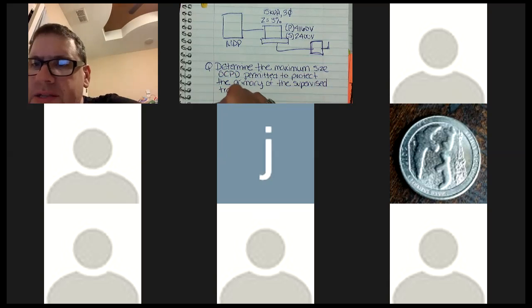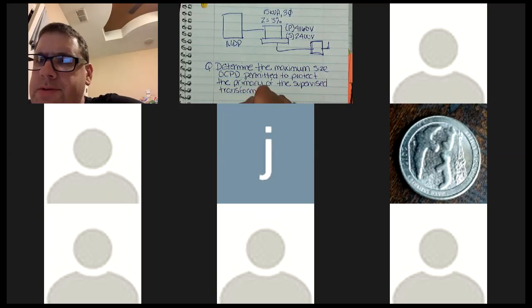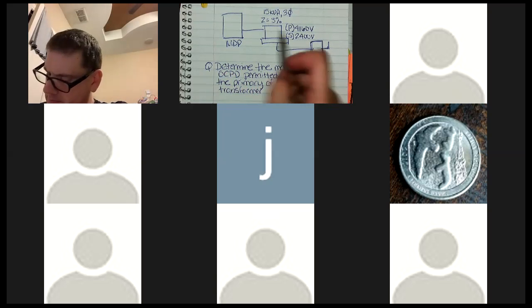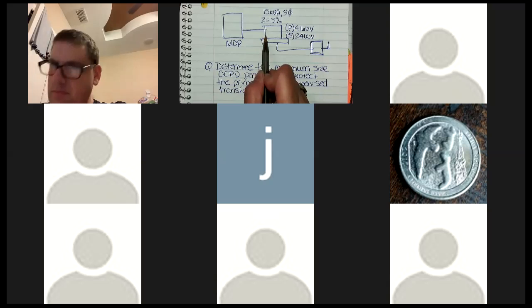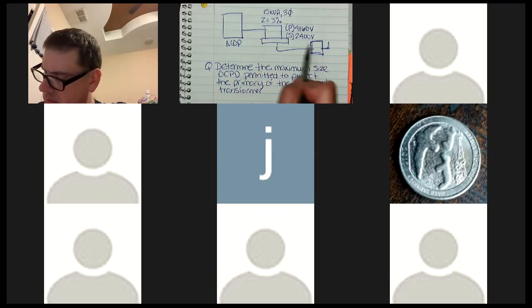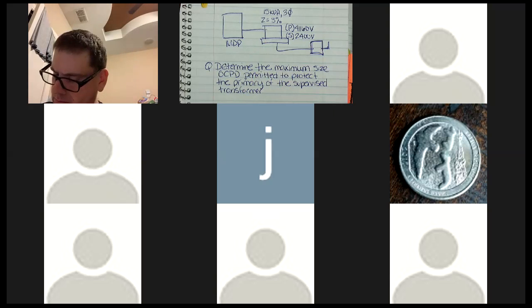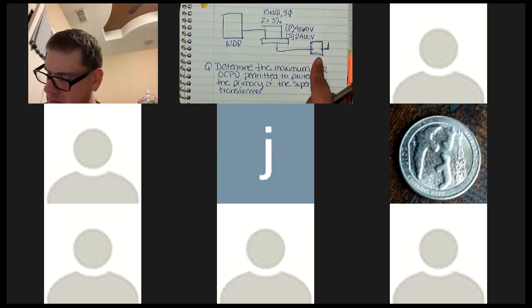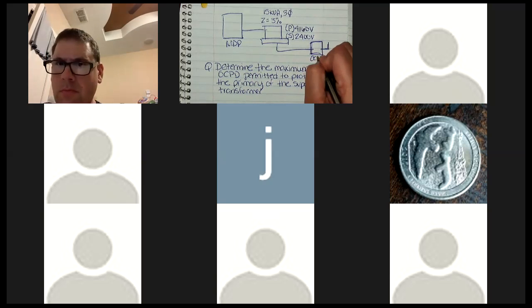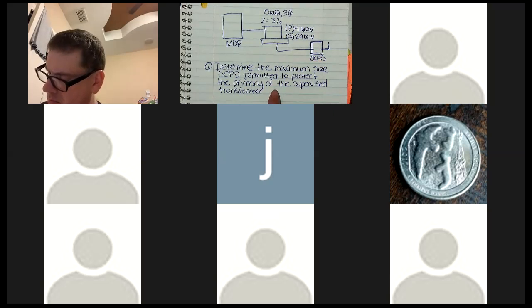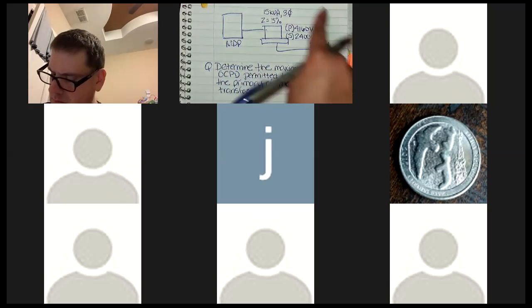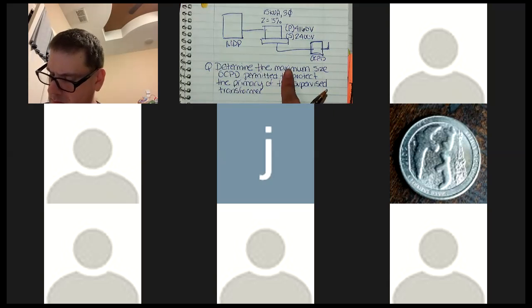Ma'am, am I reading that right? The secondary is at 2400 volts. Okay. You're coming in with 4160, and you're coming out with 2400 volts. So in reality, with this one, we have a disconnect. So obviously it's going to have an overcurrent protection device on this side. The question, don't let it confuse you, is just asking you for the primary. But we are going to size this as if you're doing both of them, right?